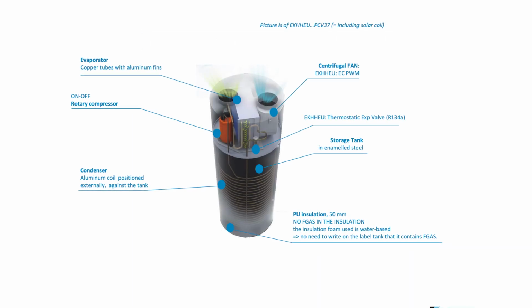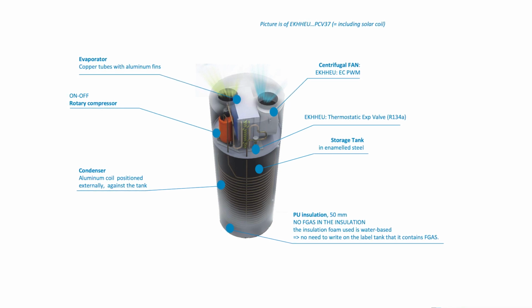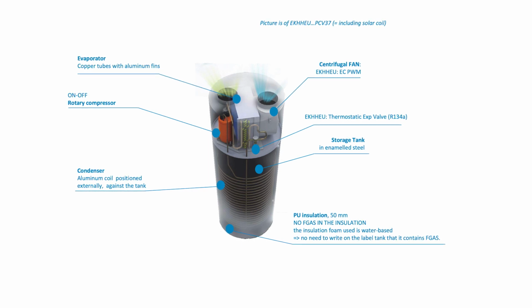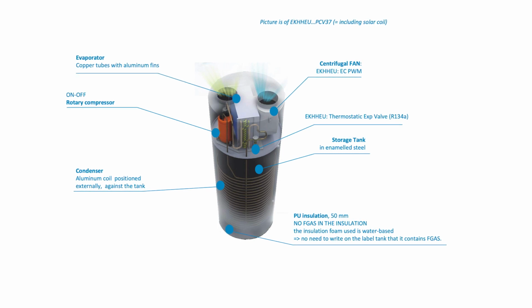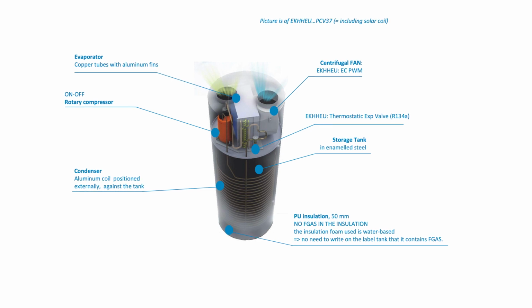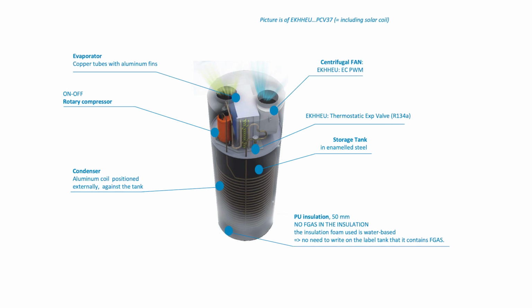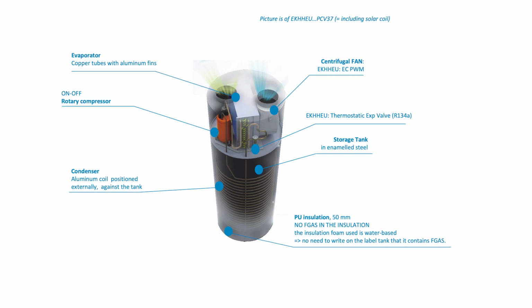When the covers come off, the heat pump at the top and the tank section at the bottom become more visible. The warm air is drawn into the evaporator by the fan, the air inlet marked in yellow, through the coil with copper tubes and fins, which is the rectangular box. Here, the heat is transferred from the ambient air to the hot water tank by means of the refrigerant cycle all year round. Even when it is freezing outside, the domestic hot water heat pump keeps hot water warm reliably for comfort and peace of mind.